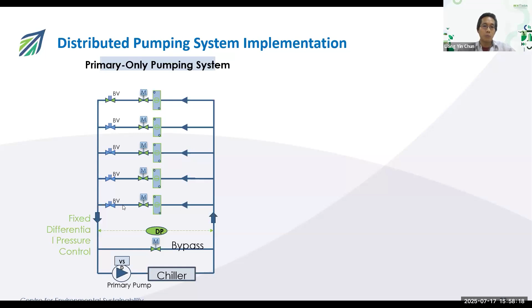And then in our system, what we do is that we actually remove all the valves, and then we add a secondary pump for each branch of the AHU. Because the Grundfos smart pump has the temperature sensor and the VSD built in, each of these branches becomes its own control loop. So they independently control the temperature within the loop. And with all the flow combined, we also downsize our primary pump, and we control it according to how much water is required in the secondary loop.